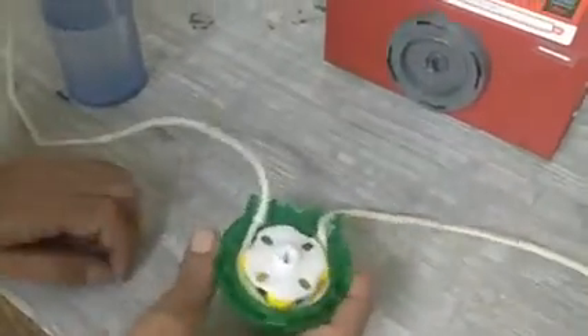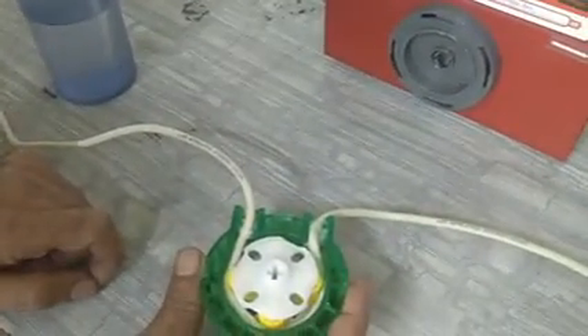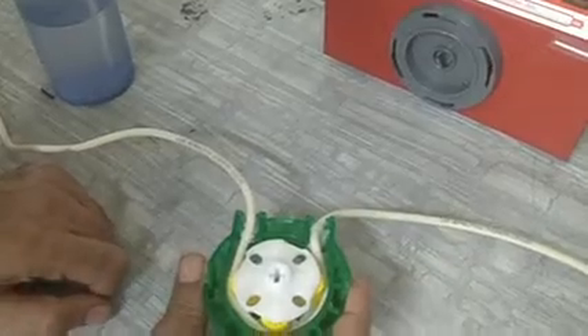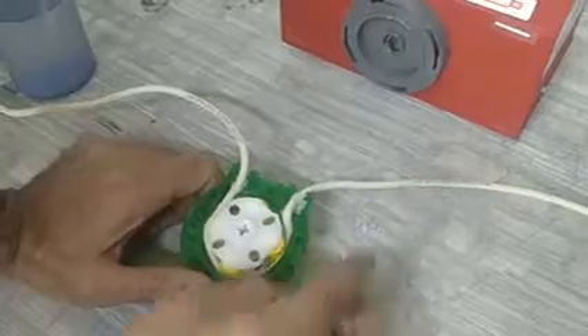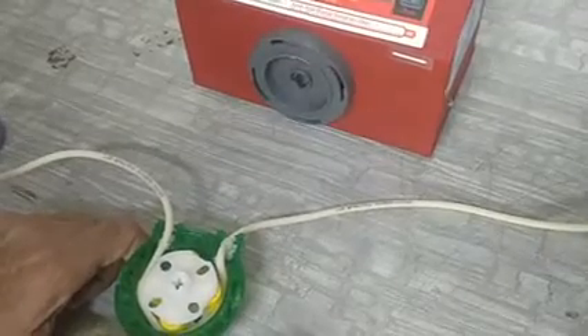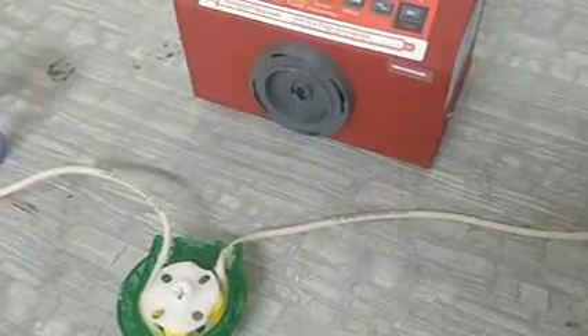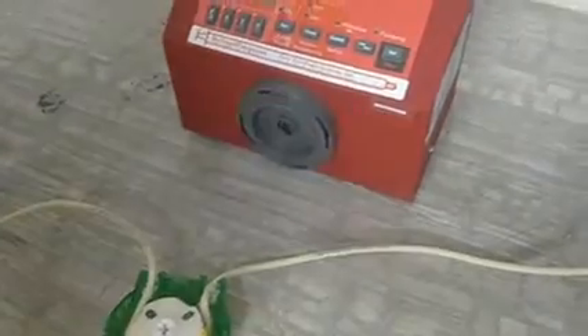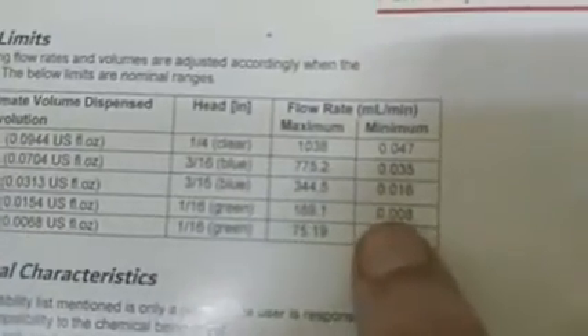So this is our tubing, and this is our head actually. In the head, the plastic part we call it cassette, and this white part we call it rotor. There are 2-3 types of heads. This head is a green head, and the tubing that we are using in this is 1 by 16 inch ID and 3 by 16 inch OD tubing, and this particular tubing gives a flow as mentioned here, 169.1 ml per minute is the maximum flow, and 0.008 ml per minute is the minimal flow.